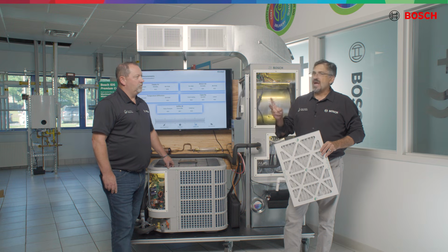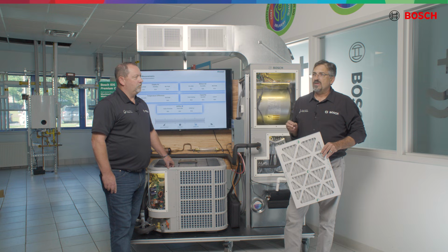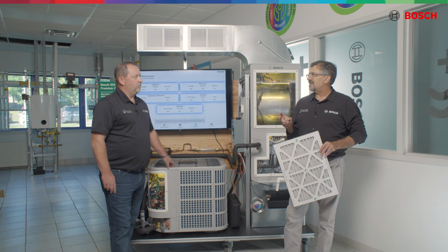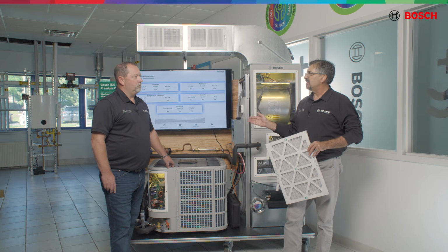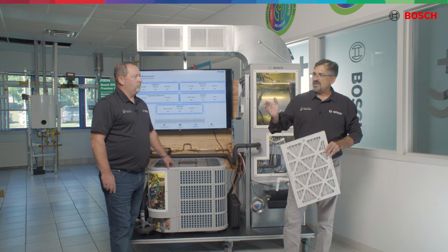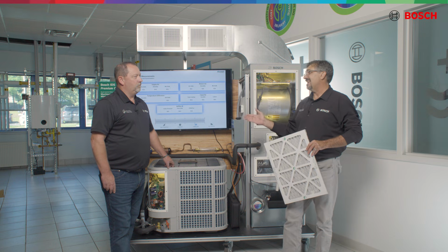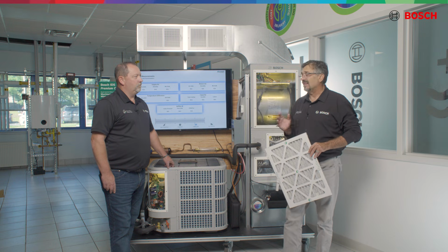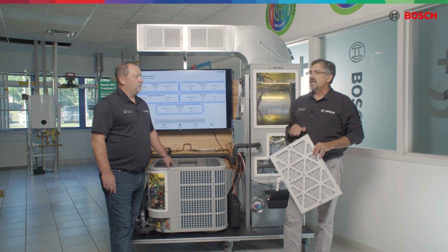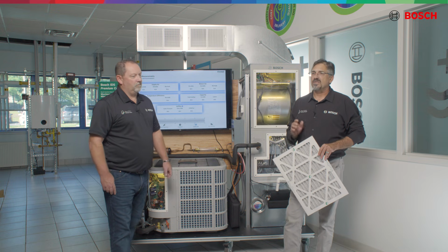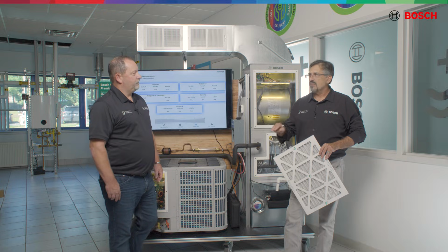Static pressure manometers, every technician needs to have one. On service calls, we need to be checking them, but also when we're installing new high efficiency equipment. We took out a 10 SEER, we're putting in an 18, 19, 20 SEER piece of equipment. A lot has changed in our industry. If we continue to overlook ductwork and static pressure, we're starting out behind the 8-ball. So remember, improper airflow can be detrimental to the Bosch heat pump system's performance. So don't let bad airflow get you down.